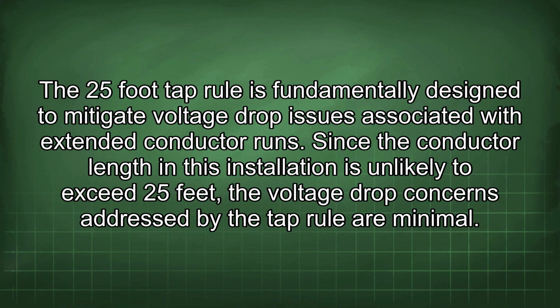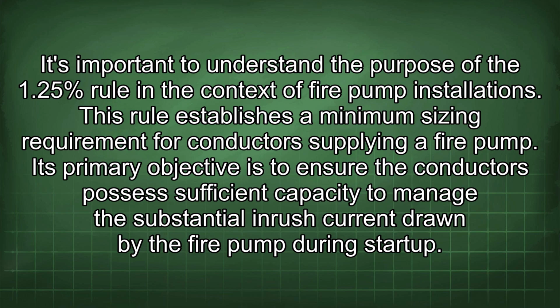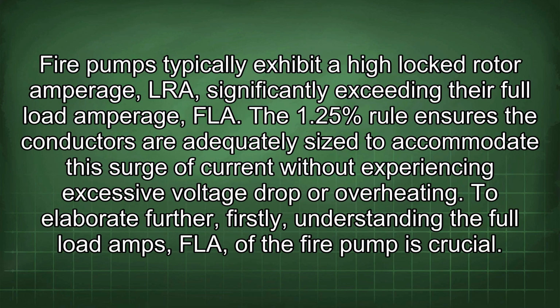tap rule are minimal. It's important to understand the purpose of the 1.25% rule in the context of fire pump installations. This rule establishes a minimum sizing requirement for conductors supplying a fire pump. Its primary objective is to ensure the conductors possess sufficient capacity to manage the substantial inrush current drawn by the fire pump during startup. Fire pumps typically exhibit a high locked rotor amperage (LRA), significantly exceeding their full load amperage. The 1.25% rule ensures the conductors are adequately sized to accommodate the surge of current without experiencing excessive voltage drop or overheating.